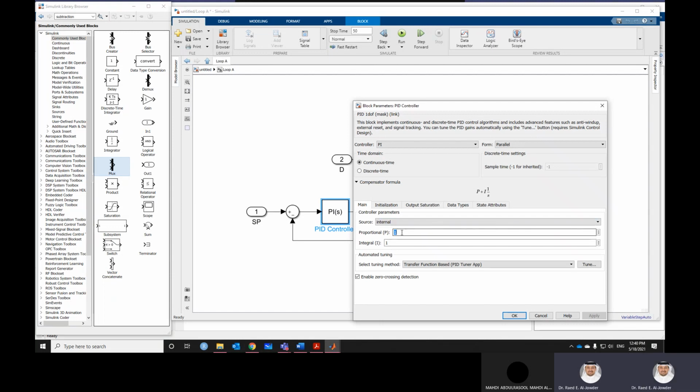Now I need to configure the controllers so that I use the controller settings that I've generated as I was calculating. So we have controller A, we have Kc. Now, remember one thing. This is Kc, and this is Kc over tau I. Just remember that when you are feeding the values. So the first Kc is 1.25. The first one is 1.25, and this is 1.25 over 1. I am putting it like this just to tell you that this is Kc over tau I.